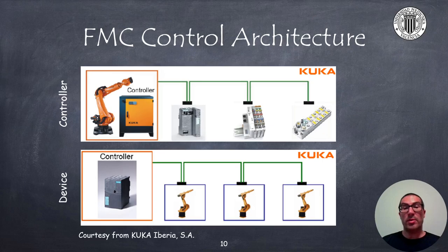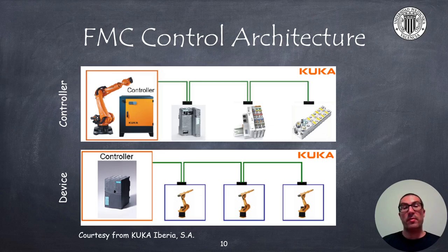Every industrial robot has an associated robot controller, which coordinates the robot's movements and handles digital signals for local process control. Industrial field buses are used when transmitting information that is more complex than simple digital signals. From a control architecture perspective, the controller can act as a controller itself, or it can act as a device being coordinated by a PLC, where the PLC coordinates the movements of multiple robots.